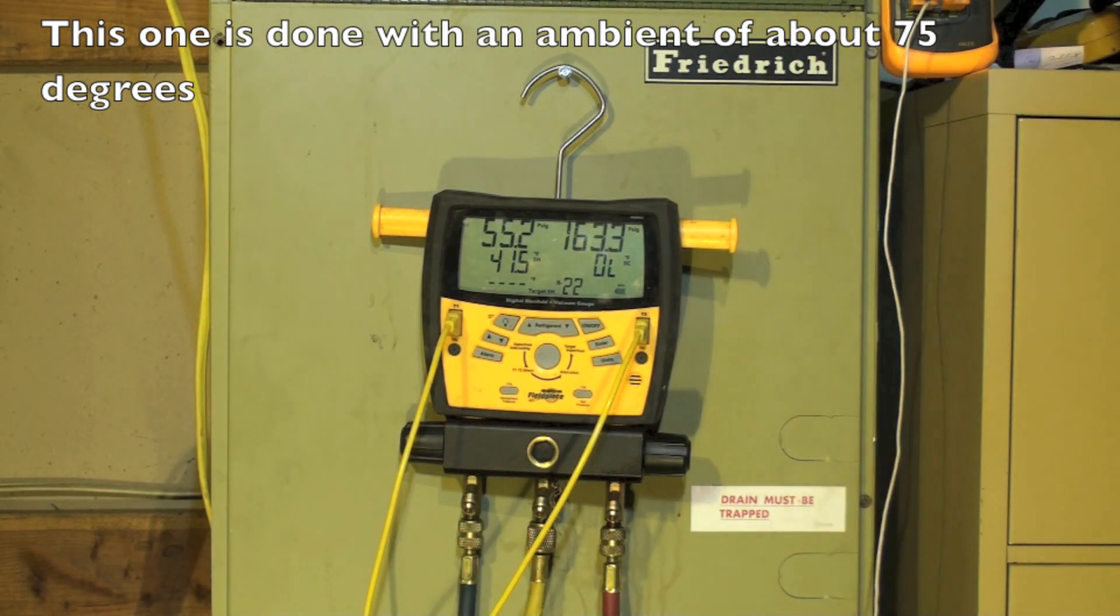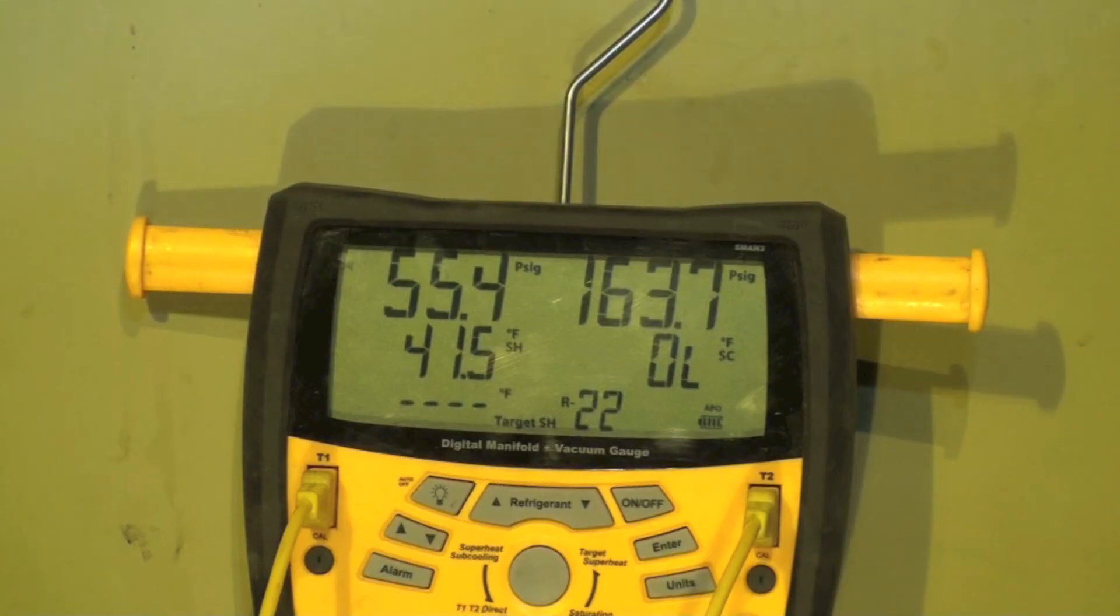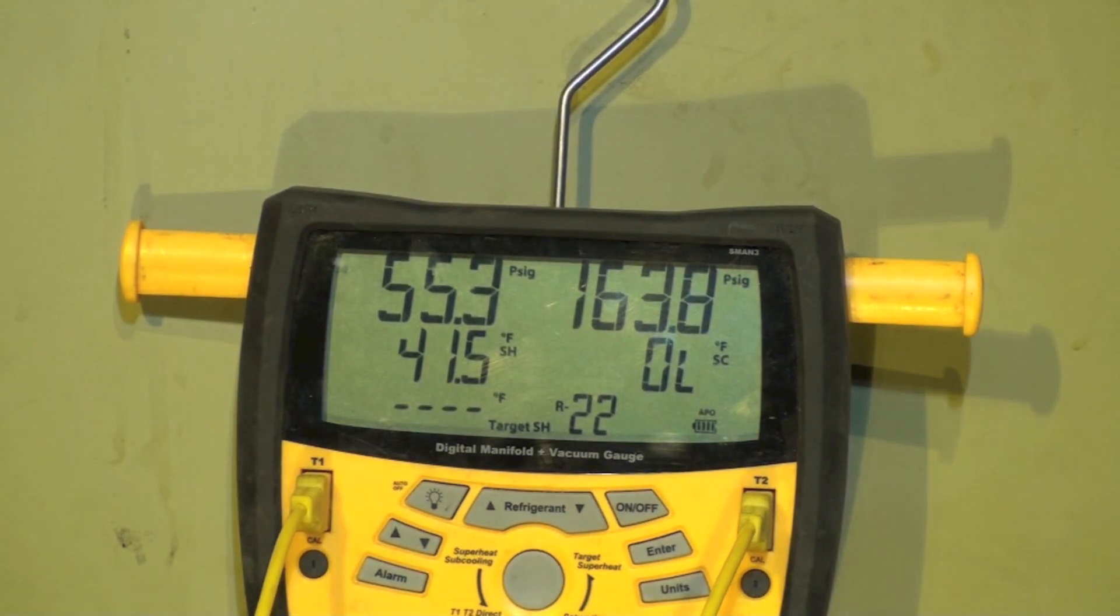This one is a couple of pounds low on refrigerant as I've done before. You can see you're 55 pounds, 45 or 41 and a half superheat and not showing any subcool at all.